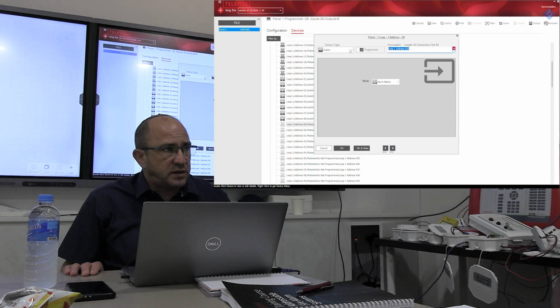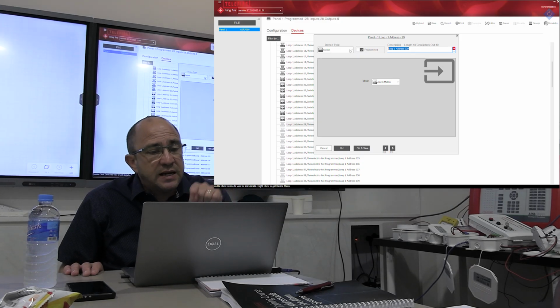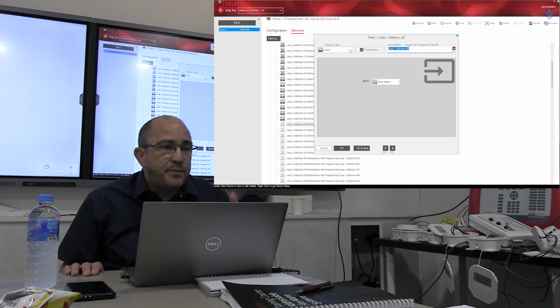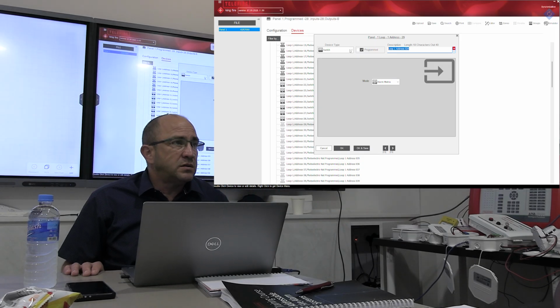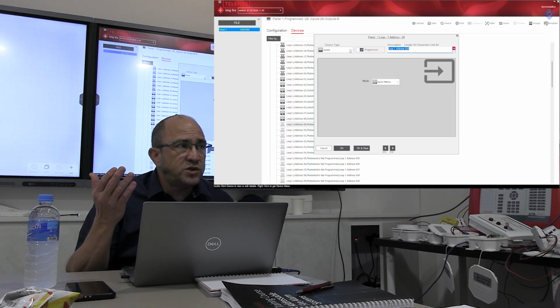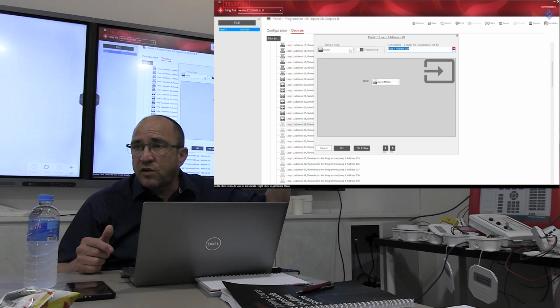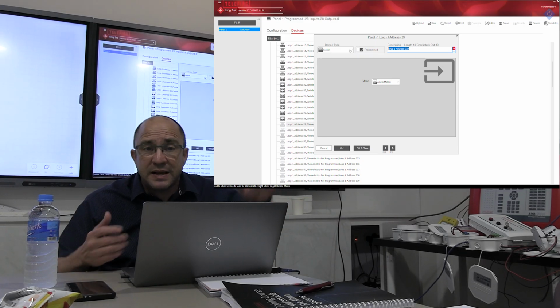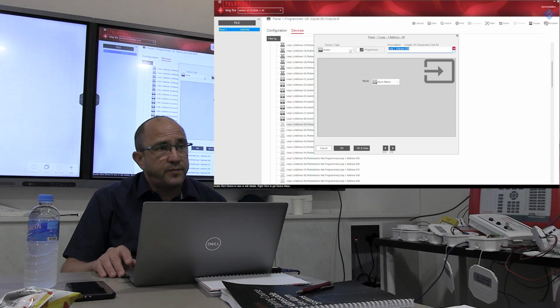If I put 2 detectors, or a push button, or a flow switch, and I put the flow switch as an alarm matrix, and I put the terms as 3 alarms, and there's a flow switch, it won't take any notice of the 3 alarms. It will bypass everything. Straight away alarm.